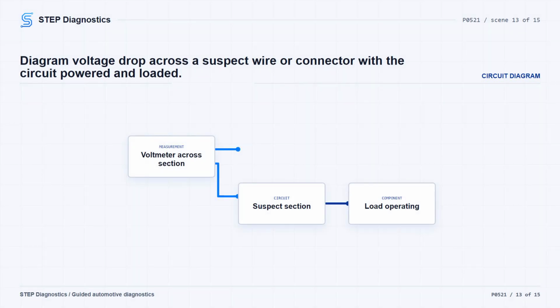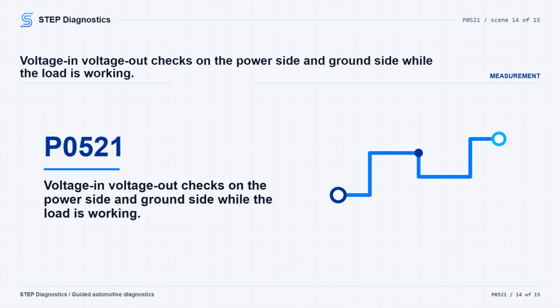For voltage drop, connect the voltmeter at the beginning and end of the suspect circuit, with the circuit powered and operating or attempting to operate. Follow conventional current flow for lead polarity. A 0-volt reading points to bad voltmeter connections or the component not being turned on. A small reading is normal circuit loss. In 12-volt circuits, that is usually less than 0.5 volts or less than 5% of circuit operating voltage. More than 0.5 volts indicates abnormal voltage loss from high resistance in wiring or connectors.